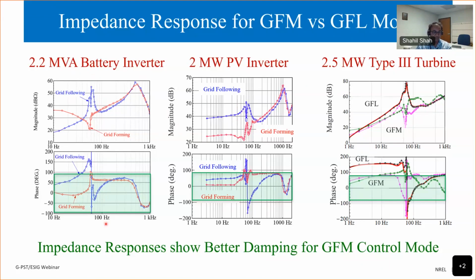For example, here in the phase responses of these devices, I am showing green rectangles, which are basically showing where the phase is between plus or minus 90. So whenever the phase of impedance of any device is within plus or minus 90, it means that the impedance has a positive real part, or it is behaving like a positive resistance and contributing positively to the damping of the system. And if the phase goes outside of this plus or minus 90 degrees, that means the impedance has a negative real part, or it's acting as a negative resistance, and it's basically reducing the damping from the system.